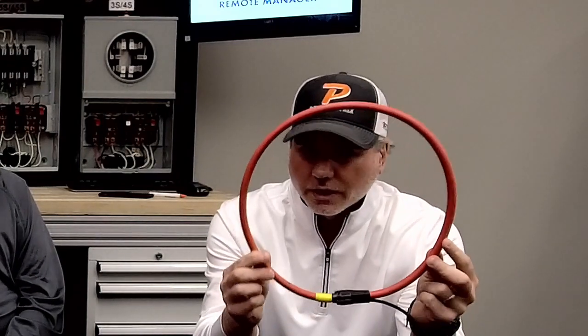This is the best technology there is out there right now that covers the widest range of installations. Rogowski coils are not perfect. The CTs, most metering class CTs are still 0.3% fully loaded. People are putting in extended range and high accuracy CTs now, which are down to 0.1, 0.15%. So when you do that measurement, this probe right here is your weak link in that measurement.